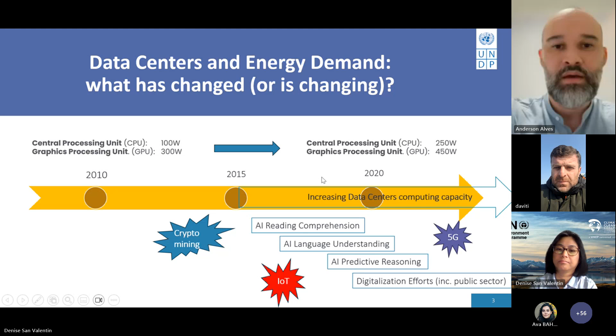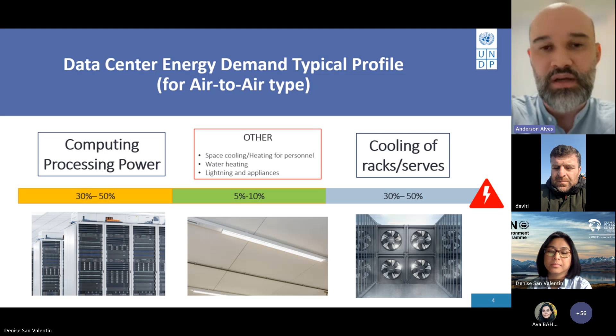Under these conditions, if you take a typical air-to-air type data center, the computing processing power would require between 30 to 50% of the energy. Cooling of the racks would require the same 30 to 50%, while remaining applications would require some 5 to 10% energy, including space cooling and heating for workers, water heating, lighting, and other appliances needed to make the data center function.